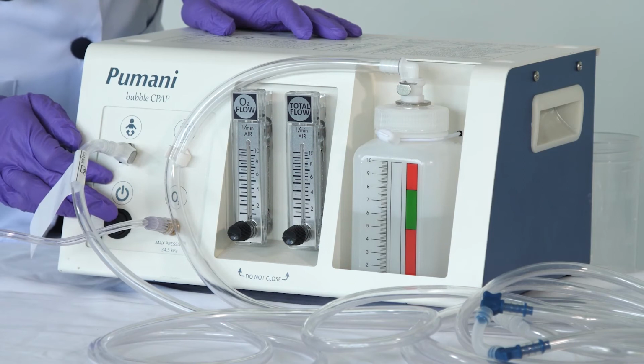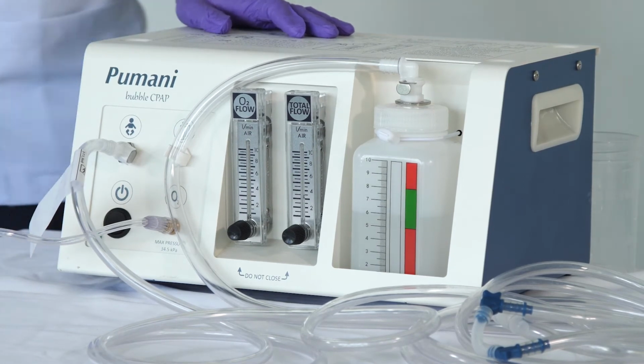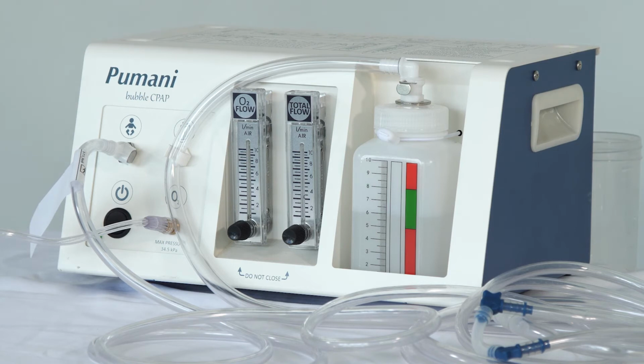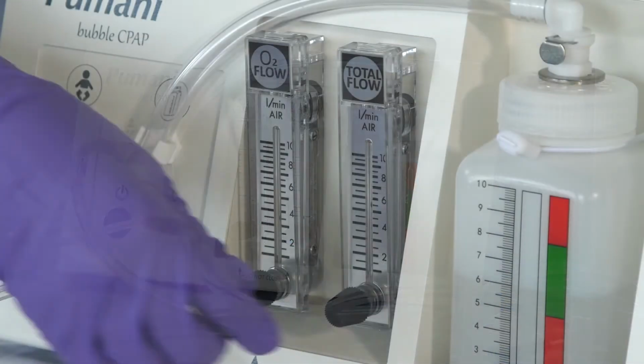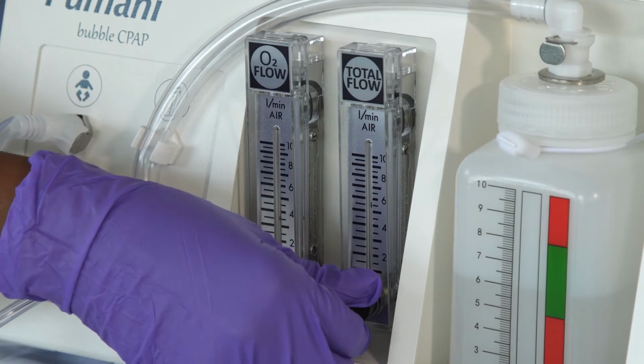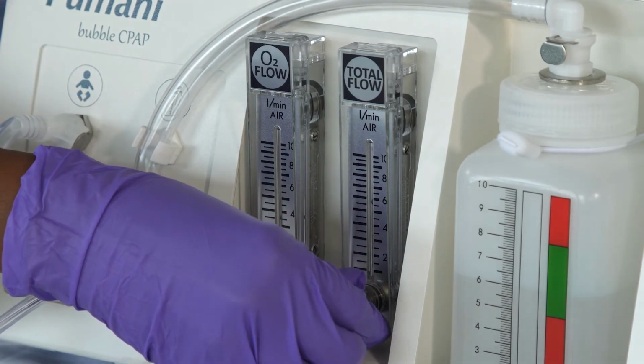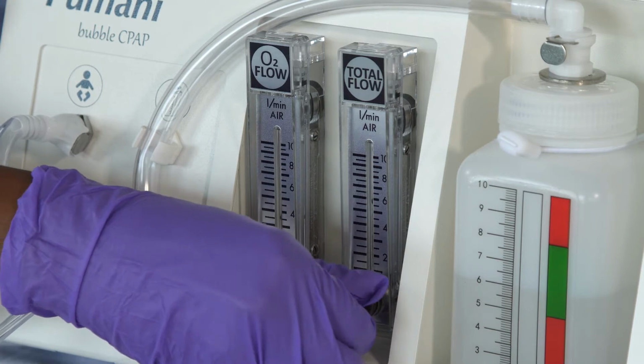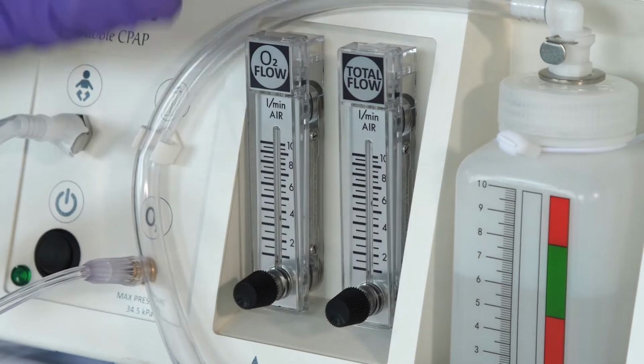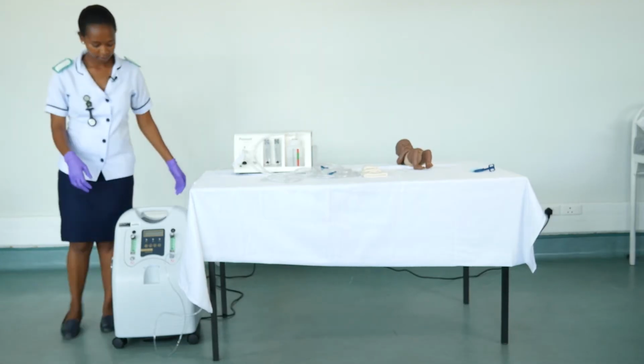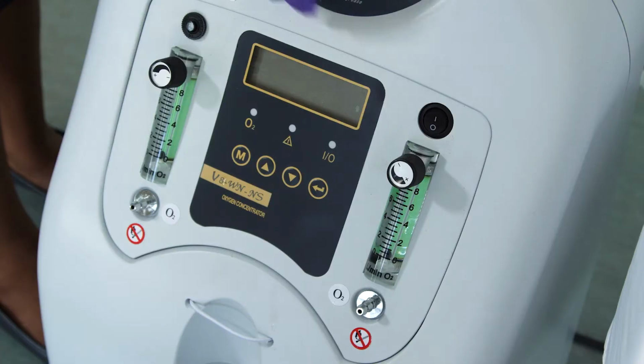We're going to switch on the CPAP machine. Next, turn on the device and check both the flow meters are open. Connect the oxygen tubing to the O2 port with oxygen connected. If you have the flow meter closed on the CPAP and then you open up the oxygen concentrator or any other oxygen source, then this can create a great deal of pressure which can blow the tubes off. That's why we leave the flow meters open on the CPAP and then regulate the oxygen flow from the concentrator.